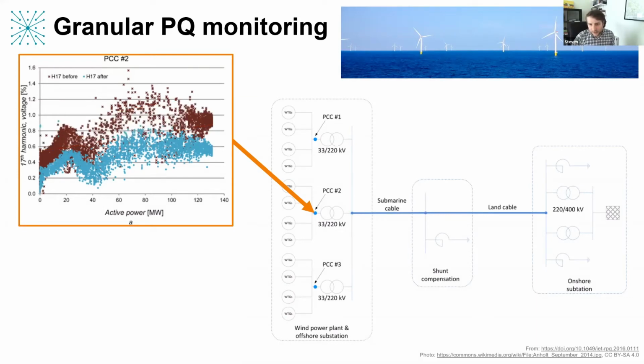And you can see that there is a cluster of activity for that particular harmonic happening at different power levels. This is a histogram of that activity over a certain period of time. This was actually due to a change in the operational behavior of the wind farm, where the impedances shifted over time and introduced a particular resonance, which meant that the 17th harmonic was promoted and amplified.